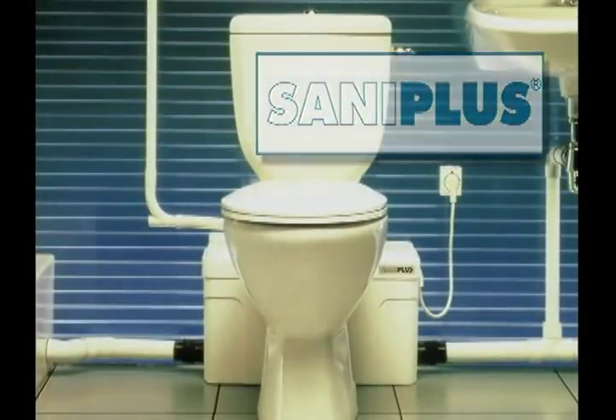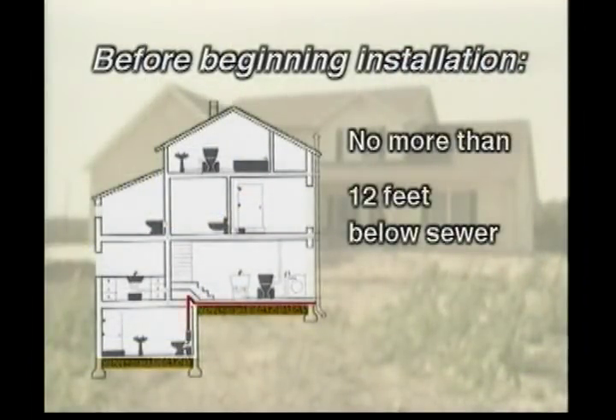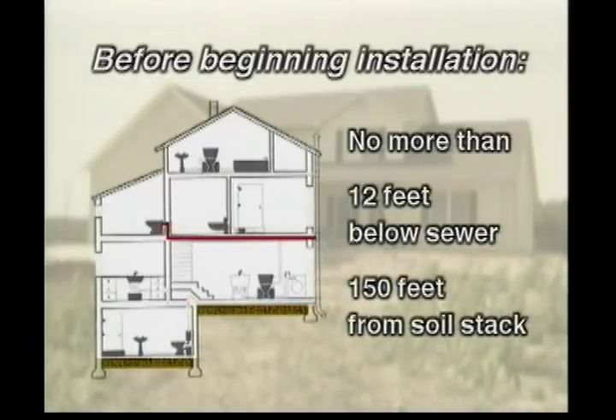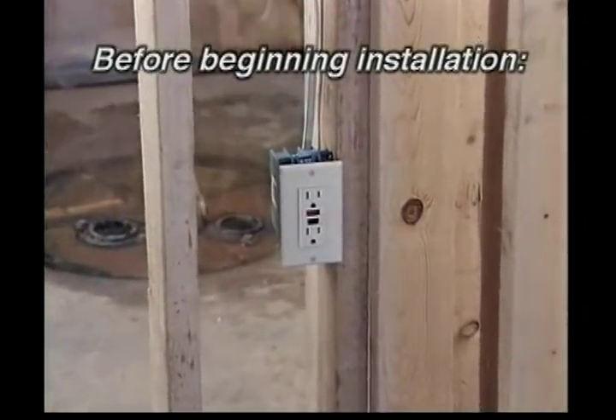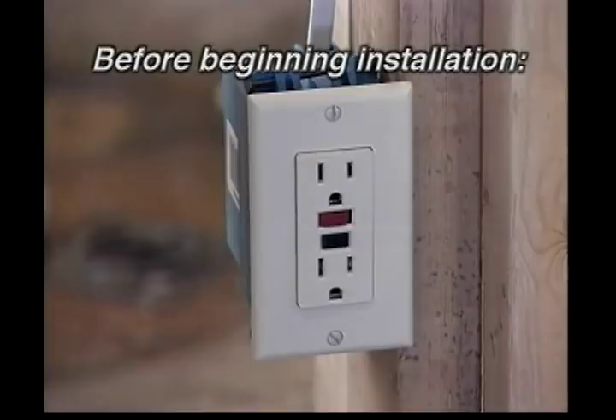Here's what your customers need to know to ensure optimal performance of a SaniPlus macerating system. Before beginning the installation, be sure that the system will be located no more than 12 feet below the sewer level or 150 feet away from a soil stack. It's also important to make certain that a GFCI electrical outlet is accessible to plug in the macerating system. Finally, note that the fixtures being connected to the macerating system must all be located on the same level of the building.